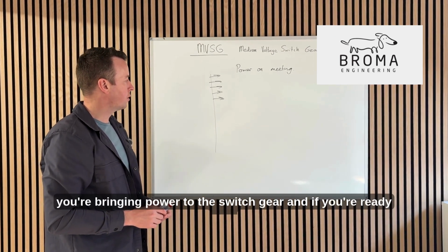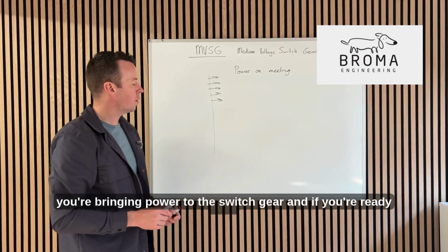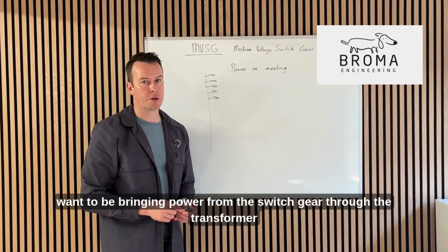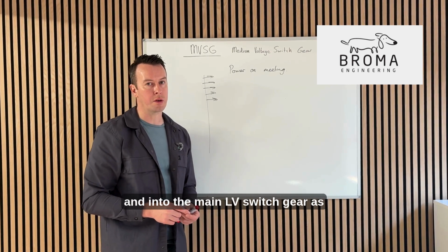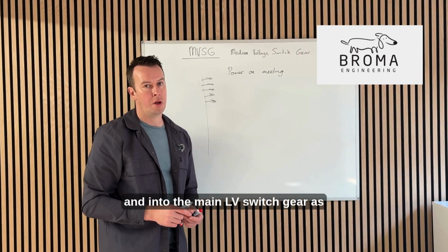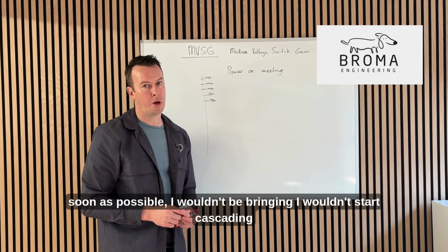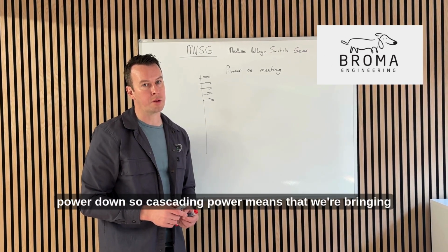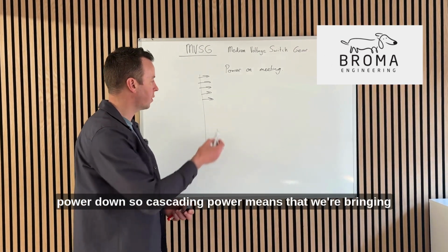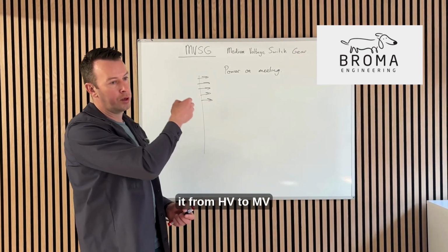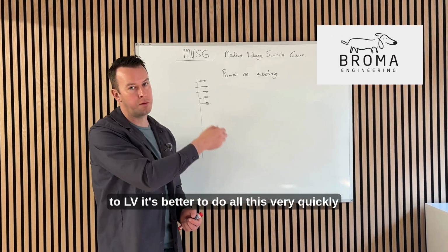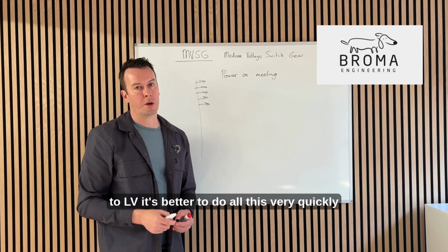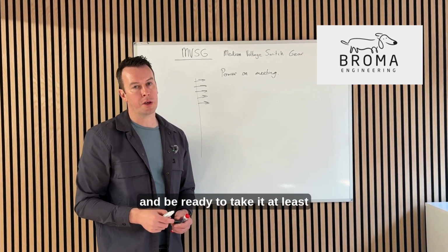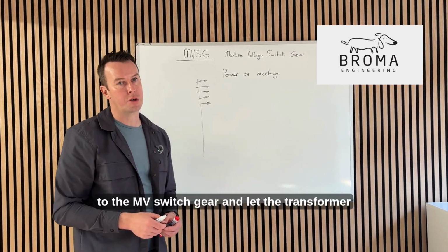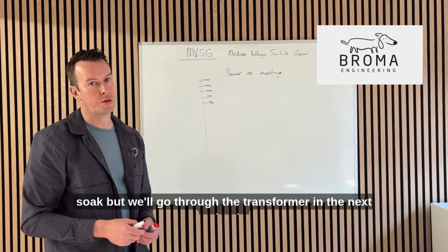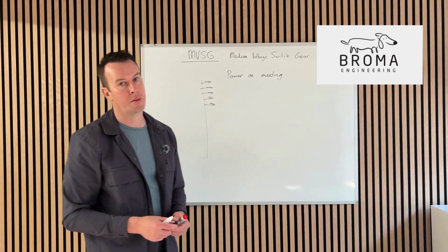You're bringing power to the switchgear, and if you're ready, you want to be bringing power from the switchgear through the transformer and into the main LV switchgear as soon as possible. I wouldn't start cascading power down—cascading power means we're bringing it from HV to MV to LV. It's better to do all this very quickly and be ready to take it, at least to the MV switchgear, and let the transformer soak. But we'll go through the transformer in the next episode.